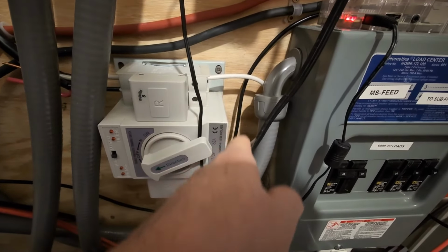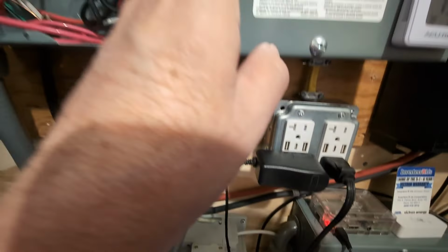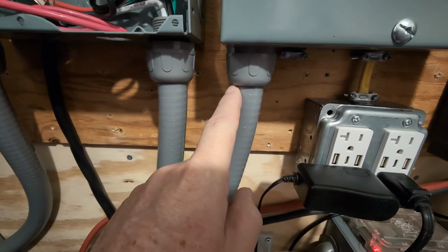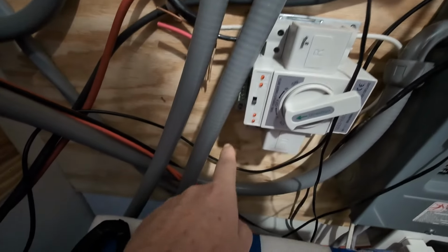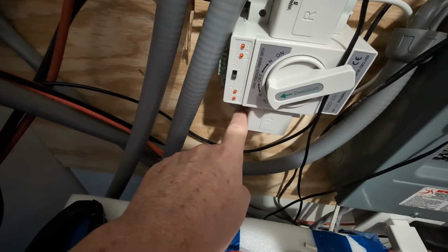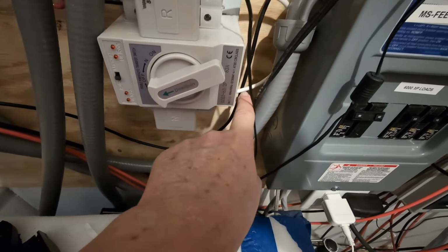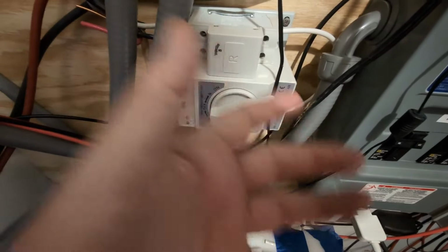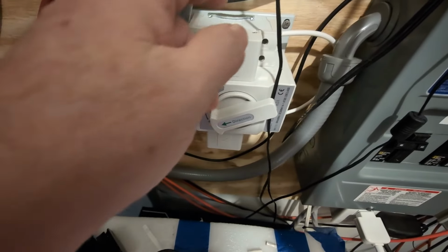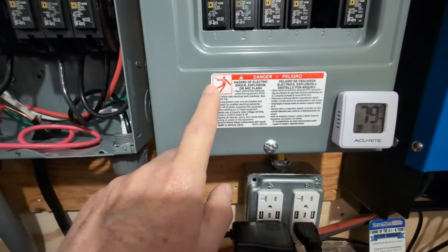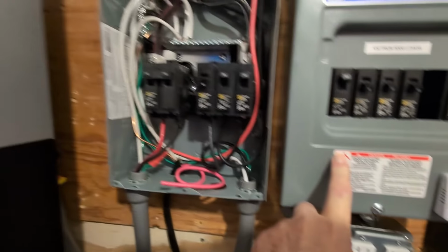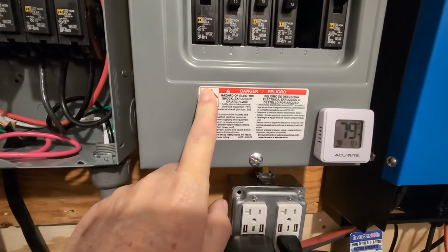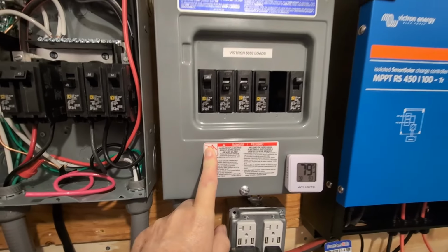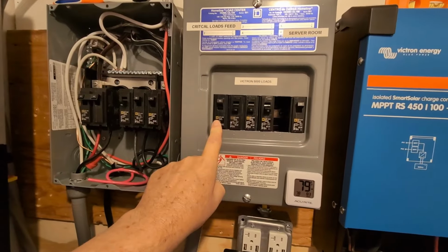So I'll need to take a cable to go from here up to feed this panel. This connector will come off. This will come in as a power source down here, and then go out as a power source out here and also out here, because there's no way these two breakers can possibly be turned on at the same time unless you take these covers off and force them. So you won't be feeding both grid power and solar power, inverter power, to the critical loads panel.